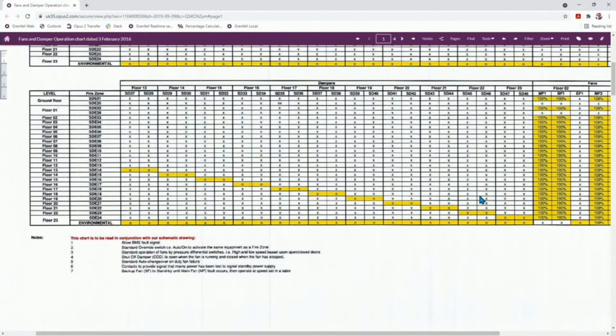But isn't it right that at Grenfell Tower, the fire zone, as you've called it, could be activated either by the smoke detector or by the fire service yellow override switch? That could only be activated once the detectors... The detector is the initial activation. So the smoke detector, on whichever level smoke is detected, activates the system. Once the system's activated, the key switch on the HMI at ground level in the entranceway can be turned to fireman's override mode. So are you saying that you couldn't actually activate it straight off from the fireman's override mode? No. None of those key switches are active until after a fire has been detected through a smoke detector and the fireman's override key switch, the master override at the HMI, is switched to the on position.